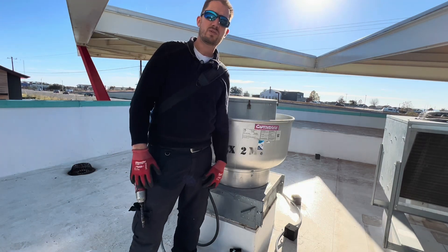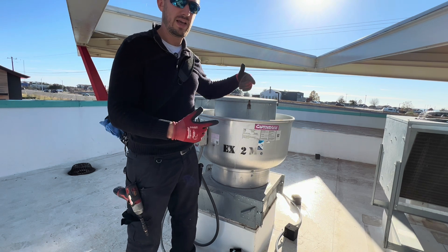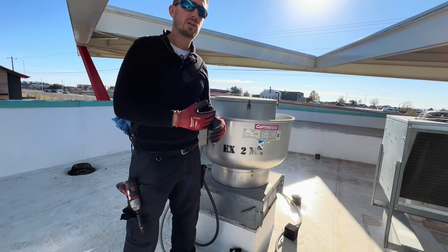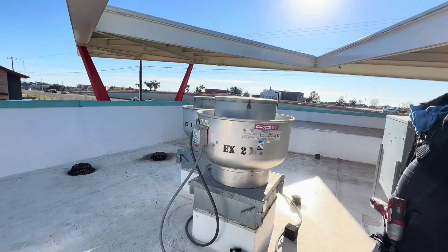Welcome back to the HVAC game. We're here today replacing this Captive-Aire exhaust fan motor. It was failing — we confirmed with tech support that the PWM signal to have the ECM motor running is arriving, but the motor is failing mechanically. We've got a new one here.